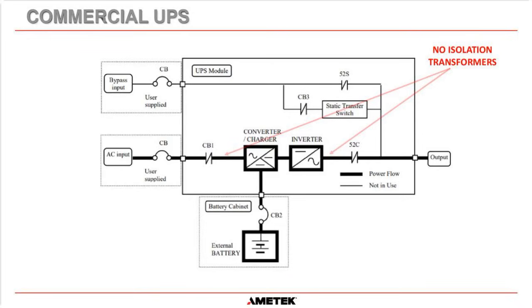And the other thing to notice about commercial UPS, and once again, one of the reasons why they are usually smaller and cheaper, is there is no isolation transformer on the input or on the output. And that's quite important, especially to stop faults propagating back onto other supplies. So for example, let's say you have a battery going in here and you have a failure in this charger section, which is a short circuit. And that allows DC to feed all the way back to the MCC. And obviously, DC getting pushed back onto your MCC is a bad thing because there are many other loads connected to the MCC that can't tolerate DC being reflected back.